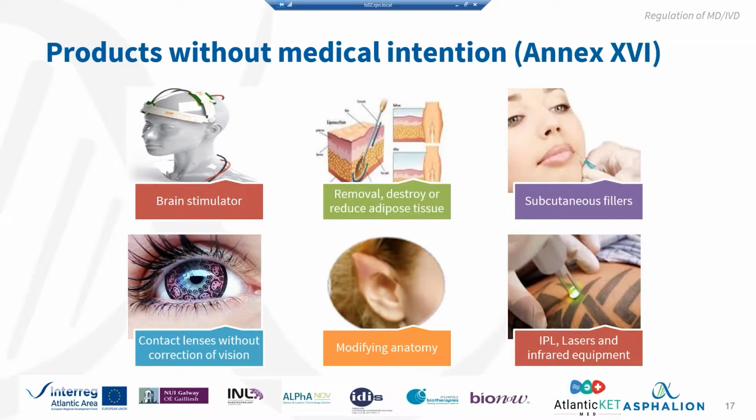One of the points that was quite addressed with this new regulation are the products without medical intention, which are described in Annex 16 of the Medical Devices Regulation. What are these products? These products lack this medical intention, but nevertheless they have to comply with the Medical Devices Regulation. Okay, what does that mean? That the requirements that are applicable to normal medical devices are also applicable to these devices, which are now considered medical devices, even though they lack this medical intention.